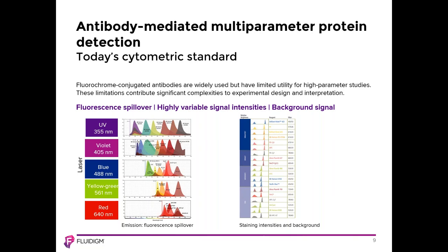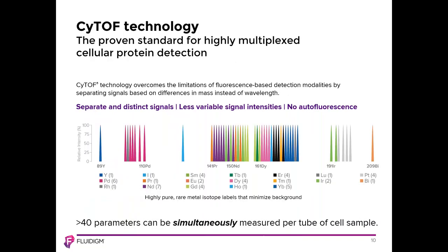Helios uses proven CyTOF technology — cytometry by time of flight — that surpasses the inherent limitations of fluorescent-based detection by using highly pure metal tags that are separated by mass instead of by wavelength. Metal tags have distinct signals which can be separated with one Dalton resolution, as well as less variable probe intensities. Nothing analogous to autofluorescence exists when using CyTOF technology, since the metals used as probes don't exist naturally in biological systems. These characteristics of metal tags provide a solution to the current challenges in high-parameter flow cytometry.